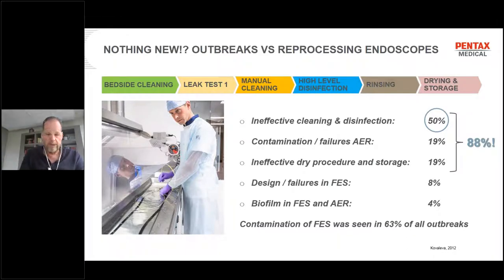Most problems and outbreaks are related to ineffective cleaning and disinfection of the endoscopes, followed by contamination or failures of the automated endoscope reprocessor, or an ineffective dry procedure and storage. So contamination of flexible endoscopes was seen in 63% of all the outbreaks.